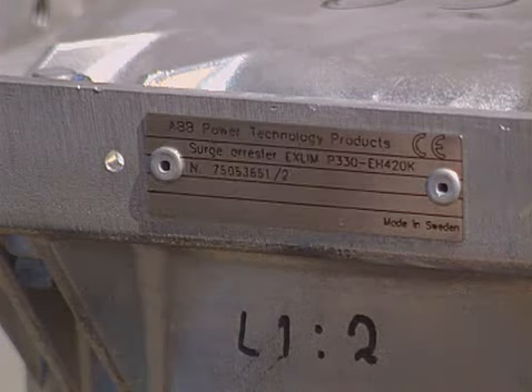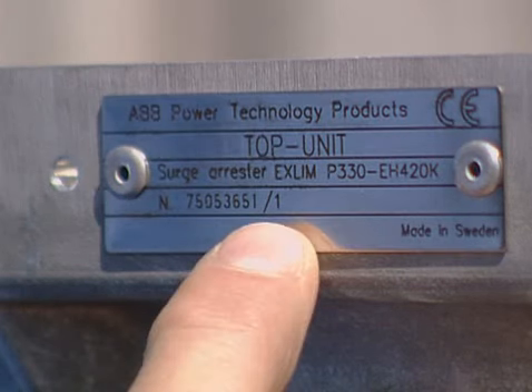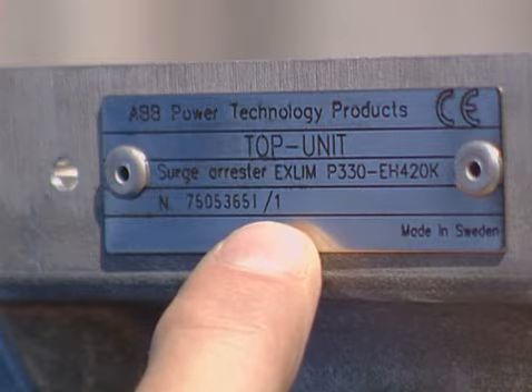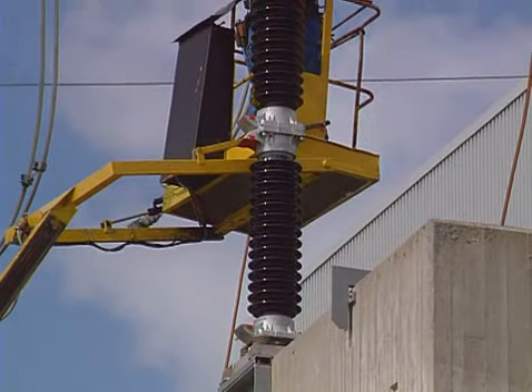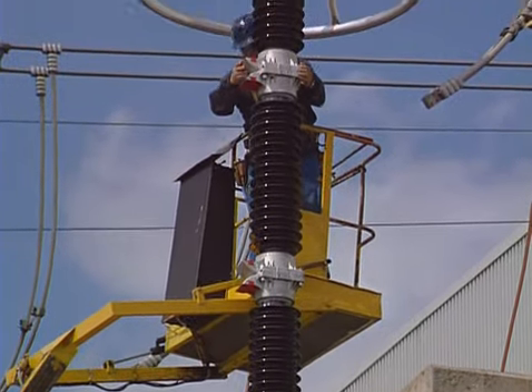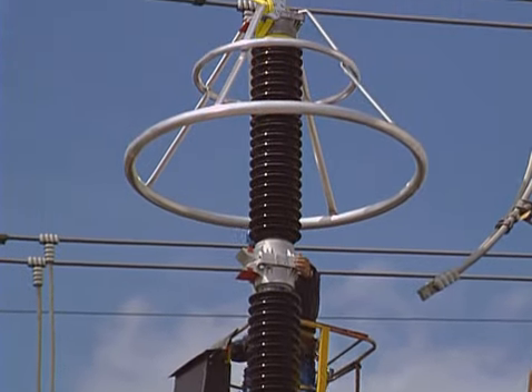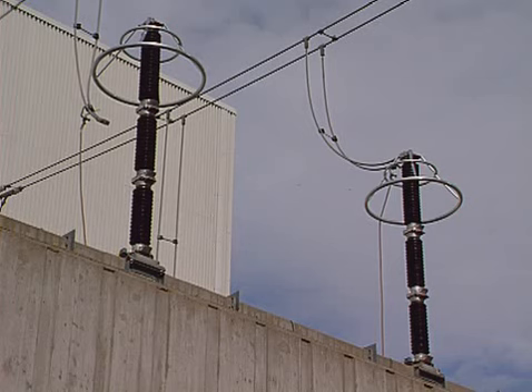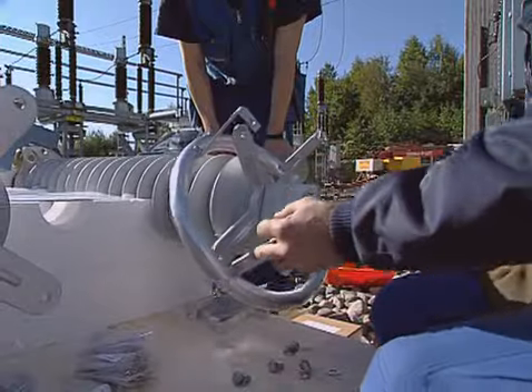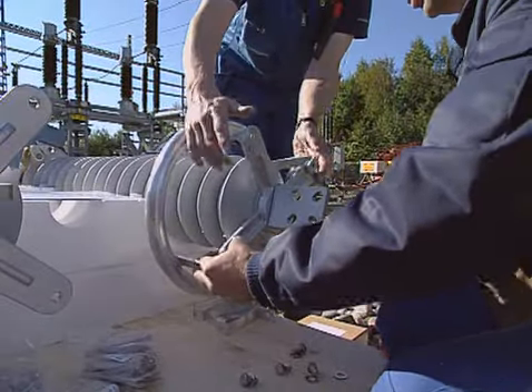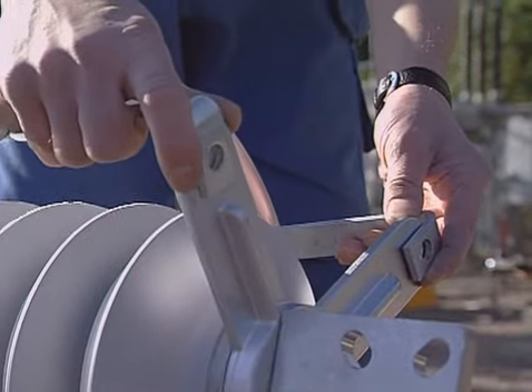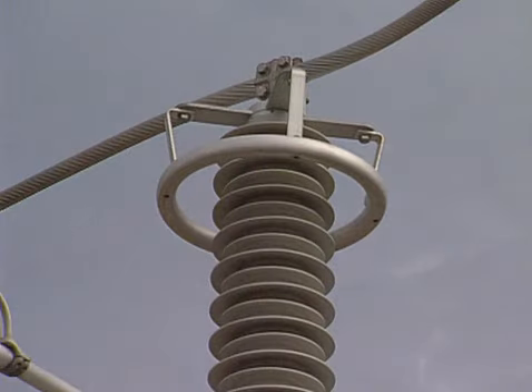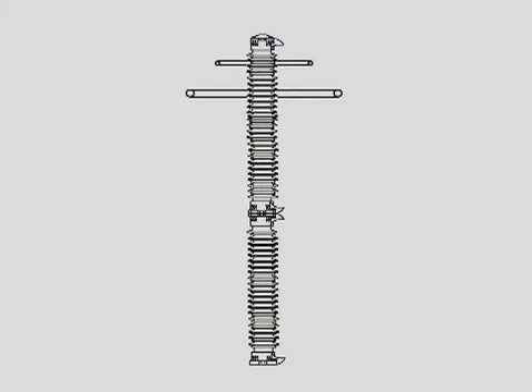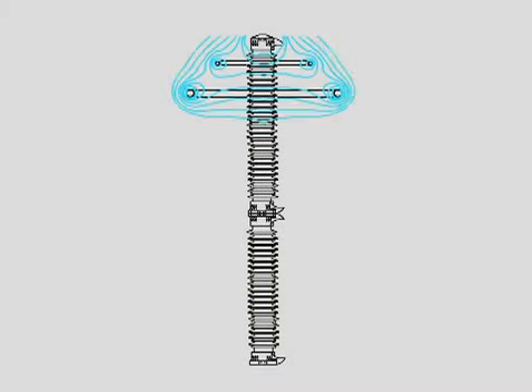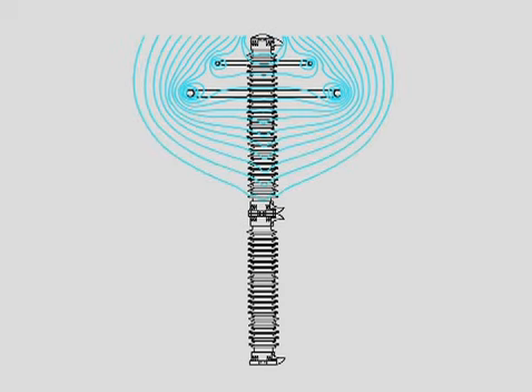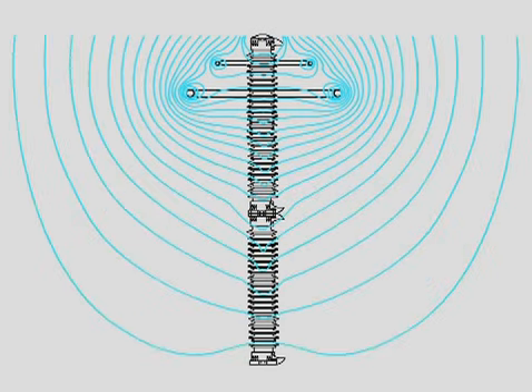It is important that the markings are followed so that the established electrical properties are fulfilled. For high system voltages or for arresters with strict leakage path requirements, simply connect 2 or more units in series. If a grading ring is included, it must be fitted in accordance with the instructions. Grading rings even out the electrical field so that voltage is distributed evenly along the entire length of the arrestor. This leads to a long service life.